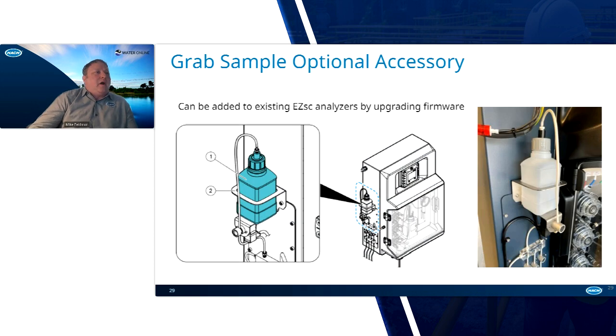Here's a part of the grab sample chamber we talked about. This is the side of the EZ analyzer, as you can see here. It allows you to put in a bottle, whether it's a standard where you can validate, which is also really important, especially if the number is higher than you hoped. Then you really want to make sure, is this a real number? It's very easy to validate the instrument. Or if you have another suitable sample from another part of the process that fits the range of the analyzer, being able to fill that vessel up and do a grab sample can make things a lot easier and avoid the lab if you don't have a lab technician or a lab instrument available.